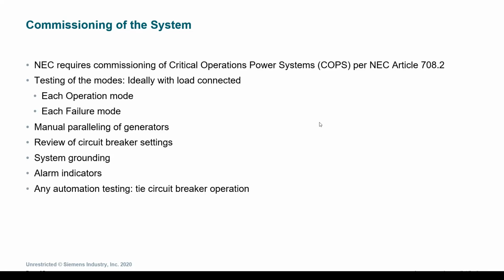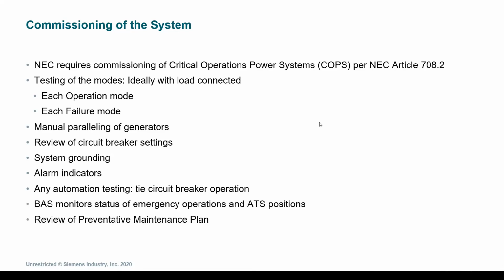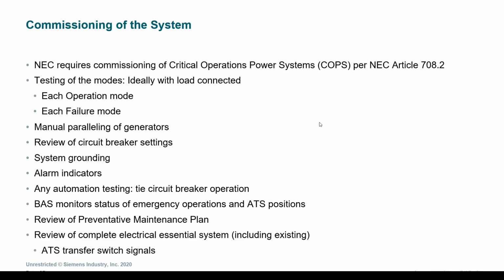As far as any automation testing, the tie circuit breaker operations is also run through a commissioning process as well. And as we discussed, the building automation system is monitoring the status of all emergency operations and the ATS positions. This is also verified as part of the commissioning process. A very important part is to review the preventative maintenance plan and to review the complete electrical essential system, including any existing that it is tying into, just to make sure, again, that the facilities team is aware of what they need to do in the long term and understand how the whole system works together.